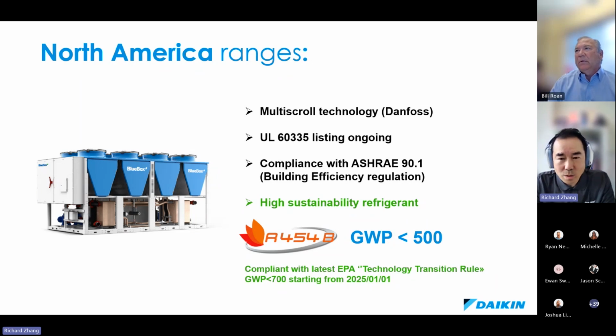When you're using the A1 refrigerant, it's not toxic, it's not flammable, so many manufacturers can introduce it to North America without the UL listing. That's acceptable because you basically check with the electrician and get the sticker onto it. But I had to bring to the attention of the Denver and Colorado engineer community: it's very important to have the UL 60335 listing when you transition over to the A2L, because it's flammable. The electrician inspection will not cover the refrigerant safety at all.